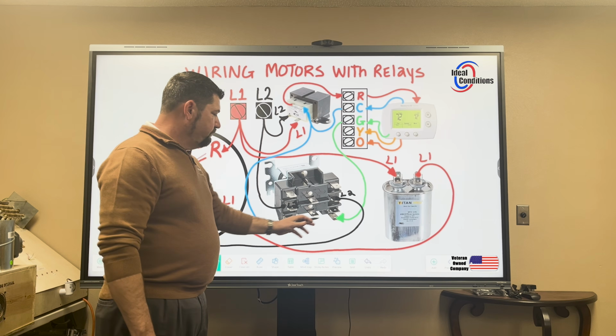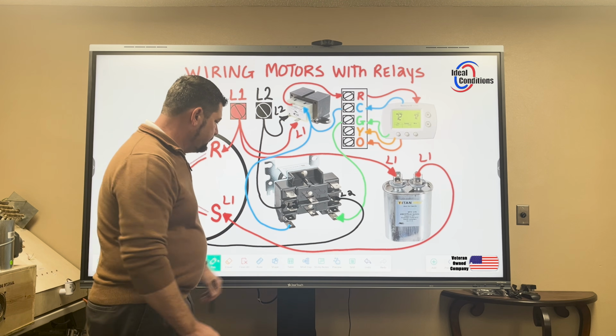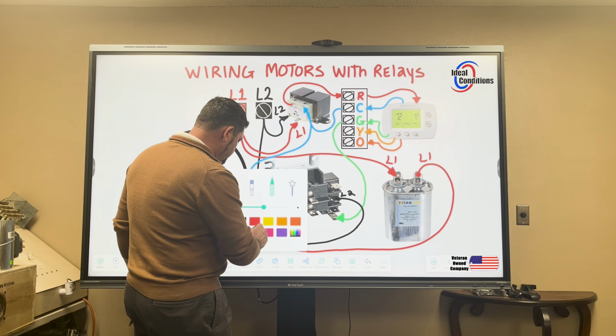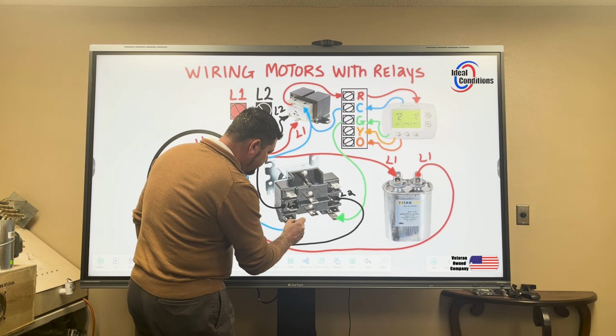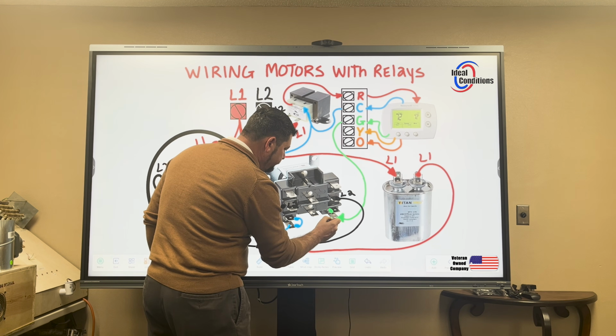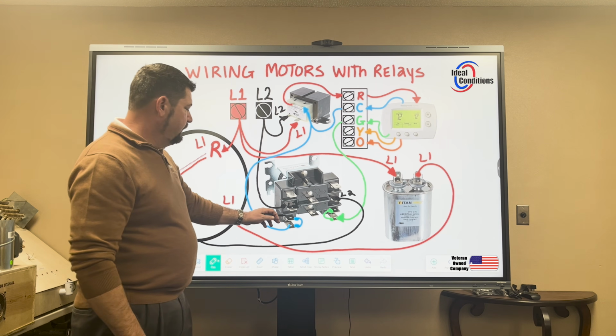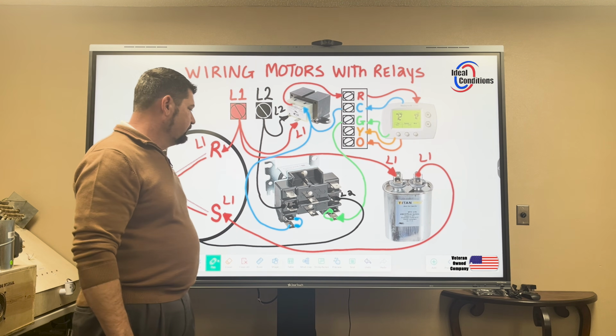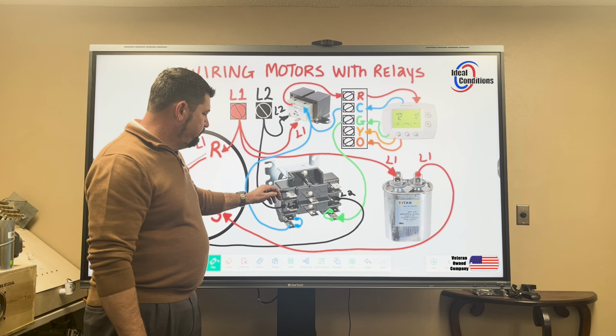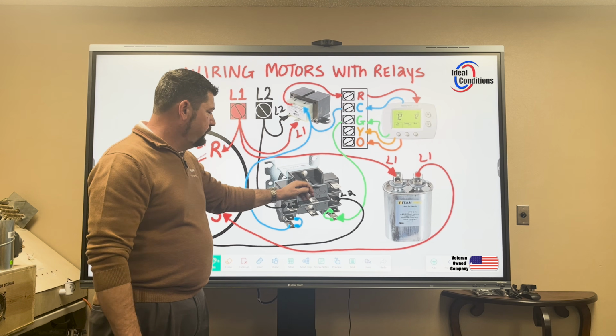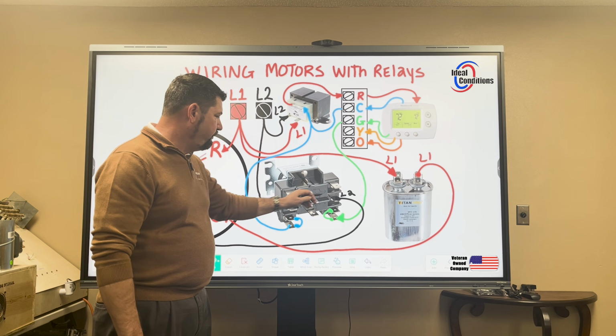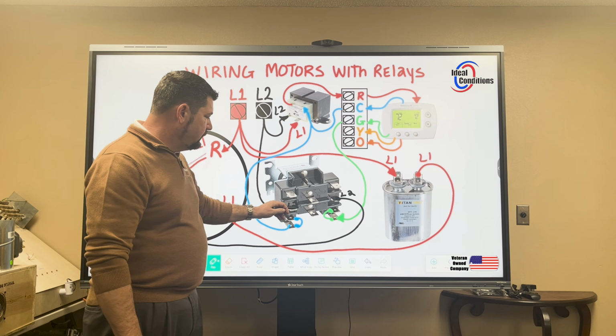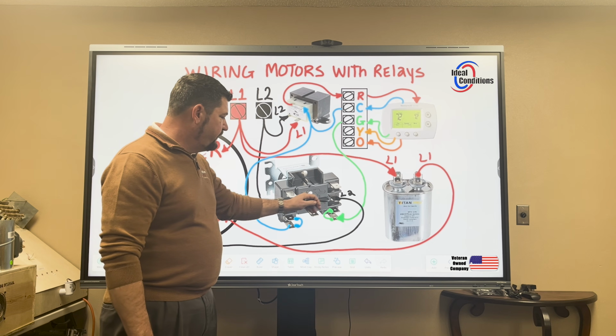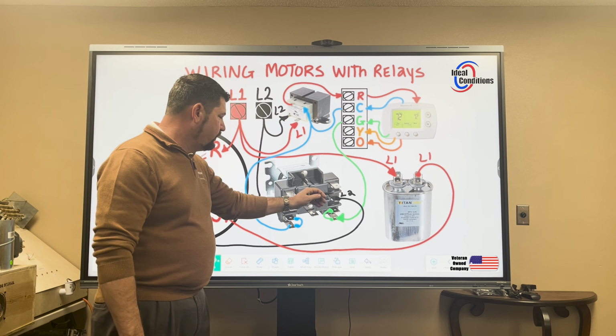So this bottom piece down here, I'm just going to mark them off in a non-confusing way. This is the same, and this is the same, so this is not a pole - this is your coil voltage. So you have pole 1, which terminals 2 and 3 switches are on, and pole 2, which is terminal 4, with terminals 5 and 6 switches on that pole.